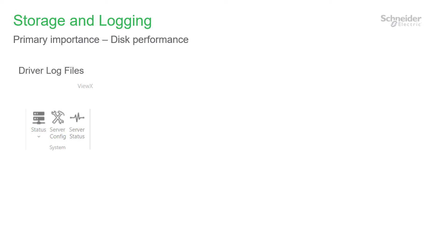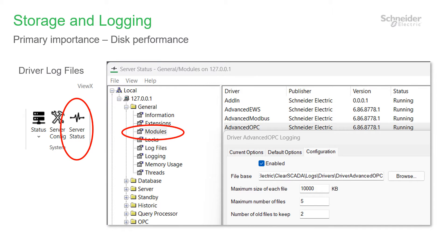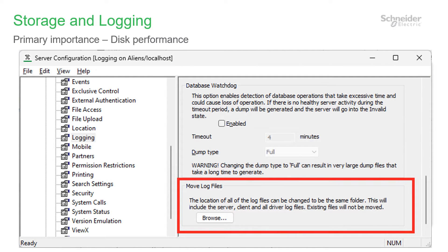The log file locations for drivers are configured on the Modules page of the server status app. Select the logging context menu and then the Configuration tab. To change all of these you would need to click each one by one. Alternatively you can change all the log files in one go using the Move Log Files feature in the server configuration tool. This will set all log locations to the same folder, including logs for the database dump files and ViewX, so you may wish to re-customize those folders.